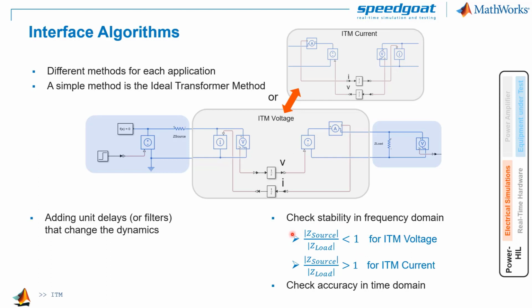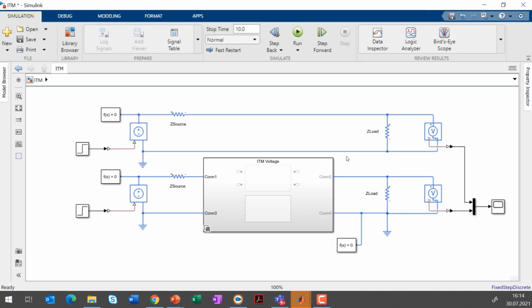The ratio of the magnitude values of the source impedance and the load impedance must be lower than 1 for the coupling shown here, with the voltage transfer from left to right. If the ratio is higher than 1, the coupling will cause instability. To avoid that, the coupling mechanism must be flipped so that the current goes from left to right and the voltage in the opposite direction.